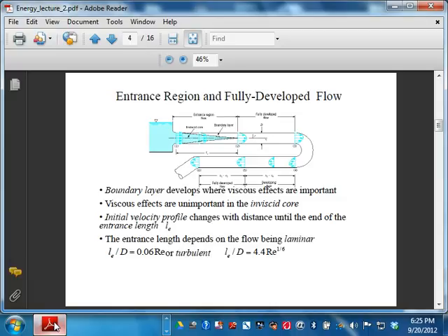So if the flow goes through a bend or elbow, the boundary layers are all a bit out of adjustment, because some parts of the pipe flow faster than others. So it takes a while to adjust. That's also called a boundary development length. You can expect that in the short region after the elbow, the pressure drop is higher.